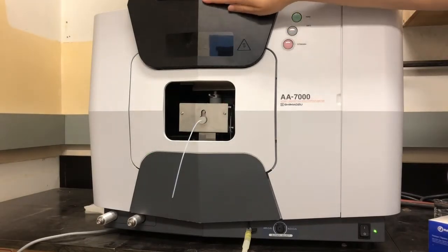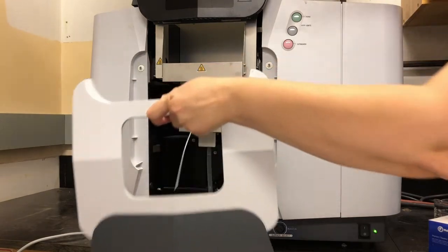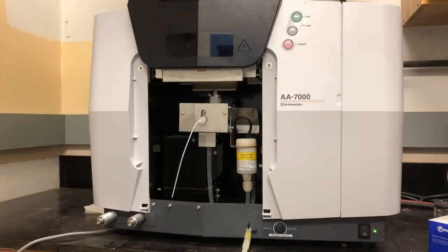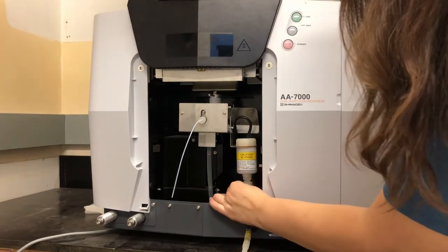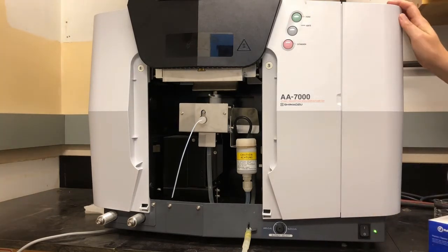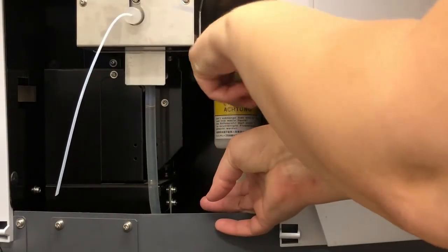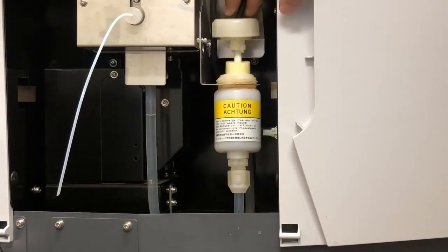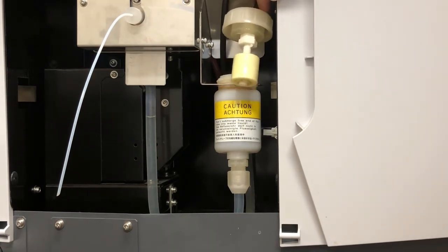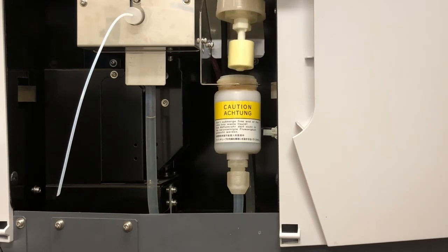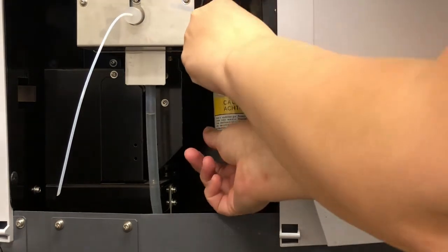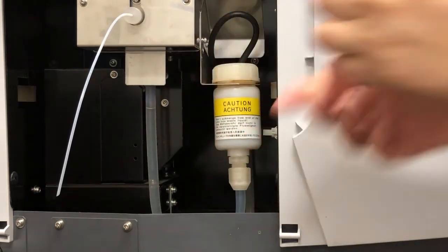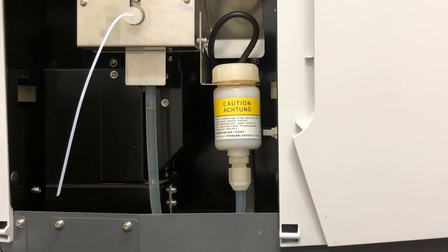Okay, so back on the machine, if we lift up the flame guard here, this little panel actually comes off. Just put that aside. And you should be able to see now a little plastic bottle inside the machine. That's where our drain sensor is located. So if I take off that cover, you'll see that inside there is the drain sensor. So it wants to make sure that that is working properly. So it wants us to lift it over the surface of the water and hit OK. And then we put it back under the surface of the water, screw it back on, and then it'll ask us to check that the drain sensor is below the surface of the water, and we hit OK in the machine as well. So there's a couple different things we have to manually do there.